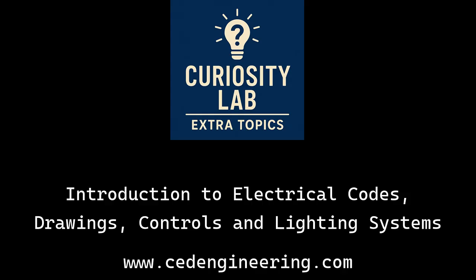Okay, so we have the right size wire for the conditions. Now let's talk about the protectors, the overcurrent protection devices, OCPDs, breakers and fuses. How do they work, and what are the key rules for sizing them? OCPDs, covered mainly in Article 240, are non-negotiable safety elements. They do 2 main things. First, protect the wires from getting too hot during sustained overloads, stopping insulation damage and potential fires. Second, they have to react instantly to massive short circuits or ground faults to protect equipment and people from, well, catastrophic events. The equipment also has a limit, a short circuit current rating, showing how much fault current it can take before it's damaged. Sizing them right is crucial.